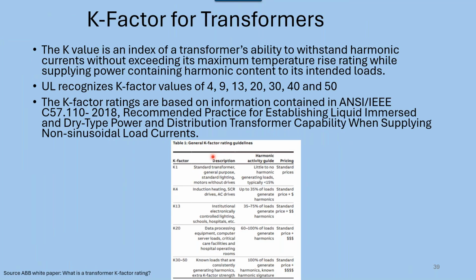All right, let's talk about K-factor. What's K-factor? When we know there are harmonics in the system, we need to design the transformer for it, okay? K-factor is an index of its ability to withstand harmonic currents. I'll talk about what's really going on with harmonics in a future slide. But the common K-factors per IEEE are 4, 9, 13, 20, 30, 40, and 50. I borrowed this from an ABB white paper. They skipped the 9th, but it's probably about 50% harmonics.